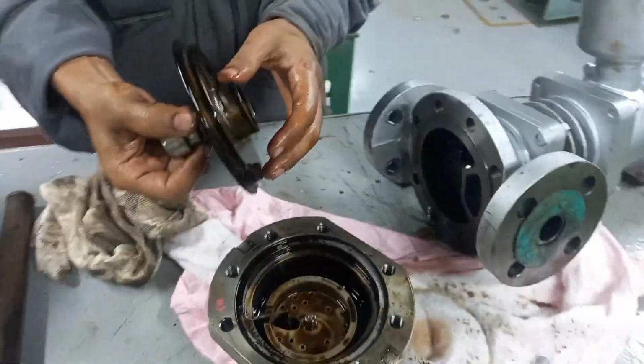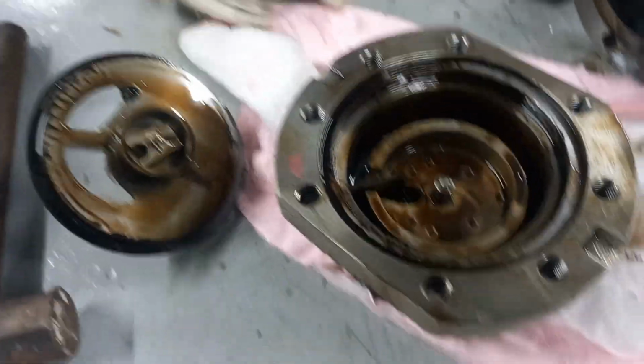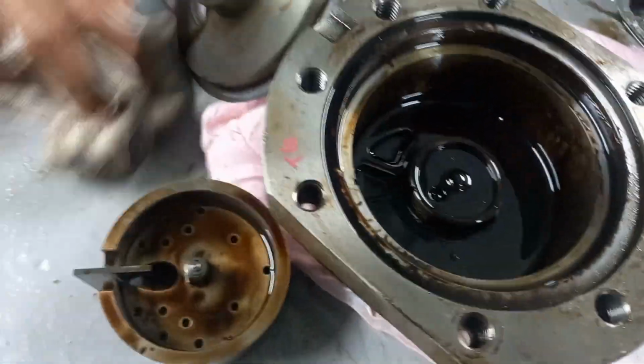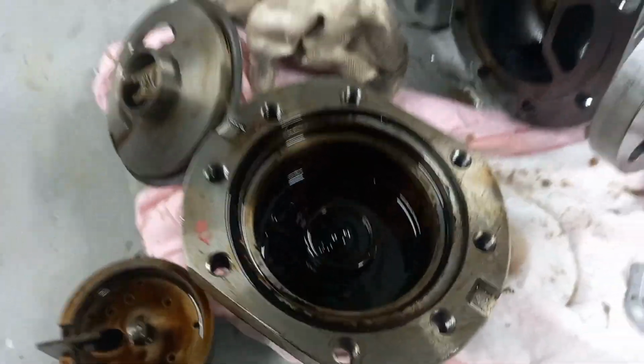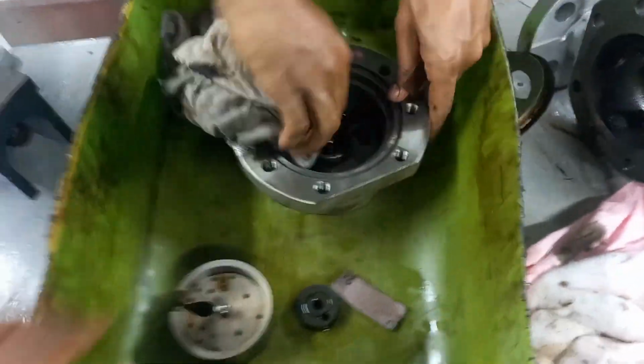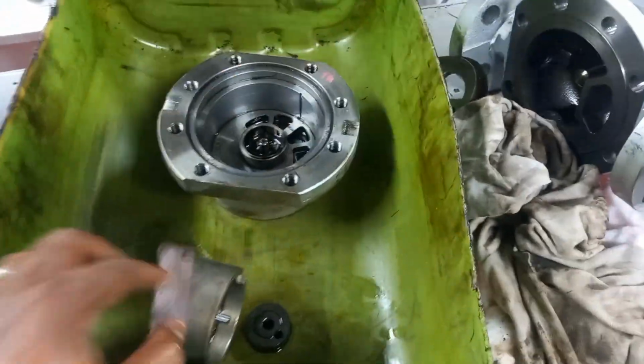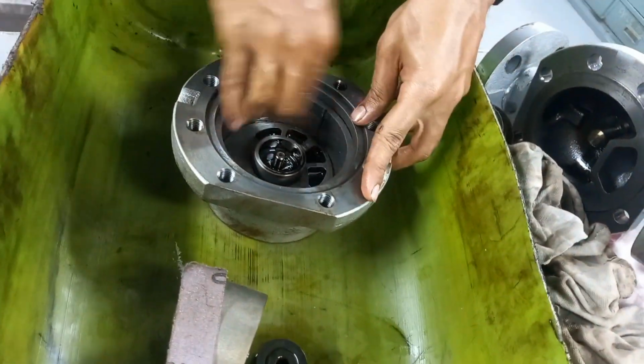Since fuel oil is the biggest operating expense on a ship, accounting for almost 70% of the total cost, the flowmeter helps the company in cost control and also satisfies charter party requirements. For maintenance, the flowmeter should be kept clean externally, and we must regularly check for any fuel oil leaks because the system operates at high temperature and pressure.